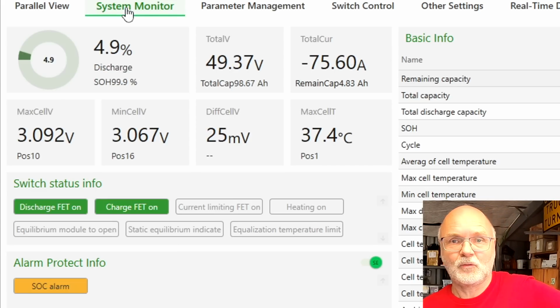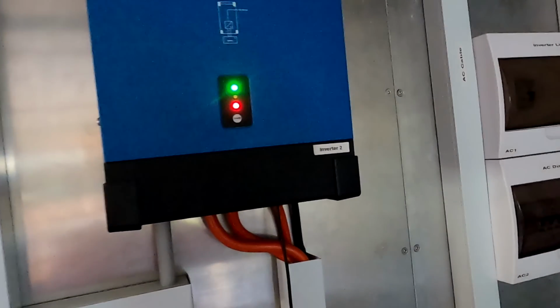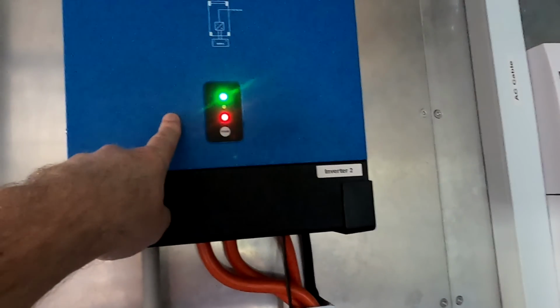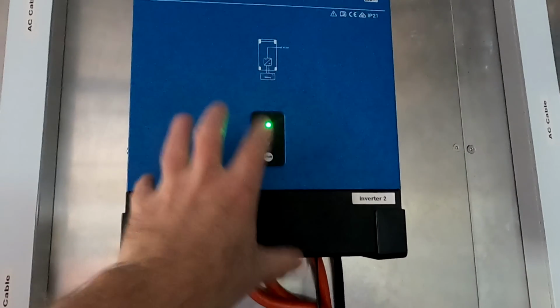I can see the Phoenix is already flashing red because we have a low voltage alarm. And this one will shut down at 44 volts. When this one measures 44 volts, it will just turn off. And I cannot change the setting at the moment because it will restart the inverter then.